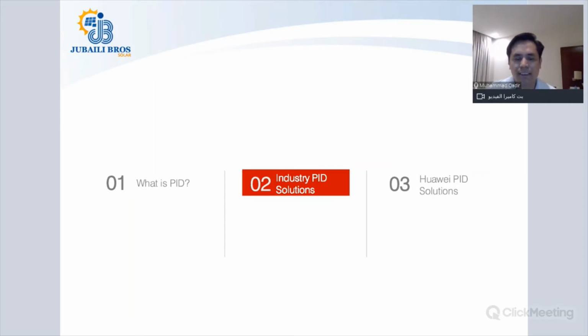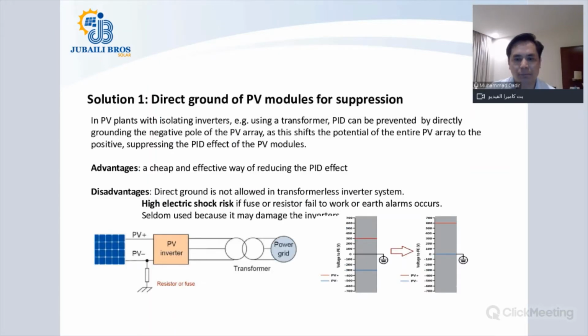So what are the industry PID solutions available? Solution one is direct grounding of the negative side of the PV module. If you are grounding the negative side of your PV module, it will be at the same potential as your earth, and therefore electrons will not escape.